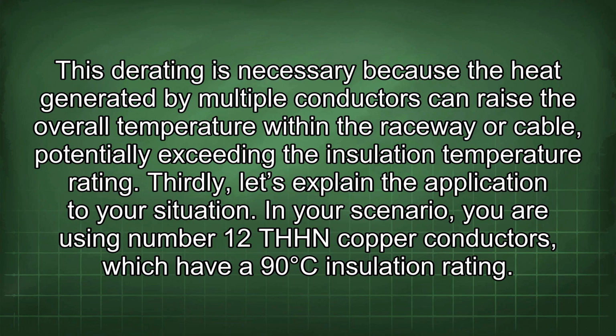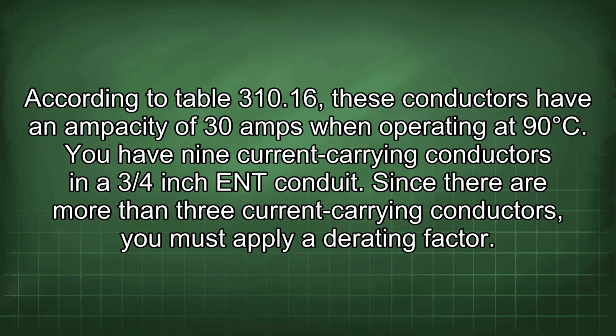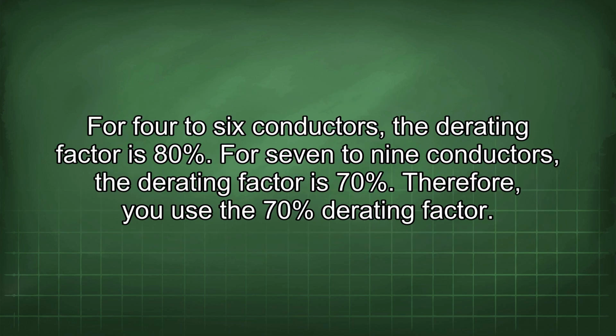Thirdly, let's explain the application to your situation. In your scenario, you are using number 12 THHN copper conductors, which have a 90 degrees C insulation rating. According to Table 310.16, these conductors have an ampacity of 30 amps when operating at 90 degrees C. You have 9 current-carrying conductors in a 3/4-inch ENT conduit. Since there are more than 3 current-carrying conductors, you must apply a derating factor. For 4 to 6 conductors, the derating factor is 80%. For 7 to 9 conductors, the derating factor is 70%. Therefore, you use the 70% derating factor.